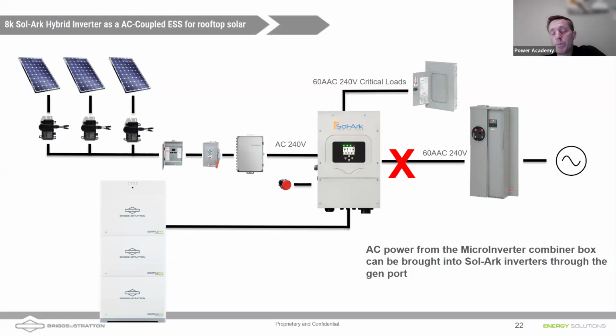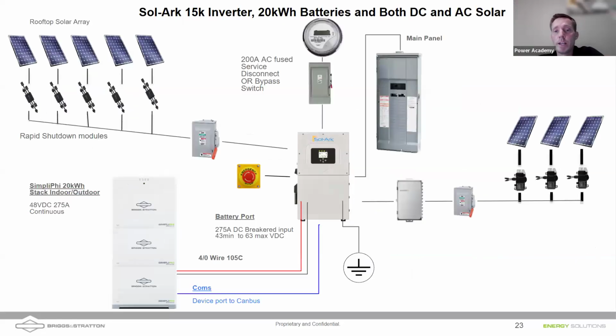Yes, I do want to point out that if we do AC couple on the load side of a solar inverter, you do not have the option of using the generator port. That is important. Don't think that just because you're AC coupling on the load side, you can still use the gen port. But Daniel and I will be telling you in a few minutes that you can integrate generators here with AC coupling, and we're going to talk about it.